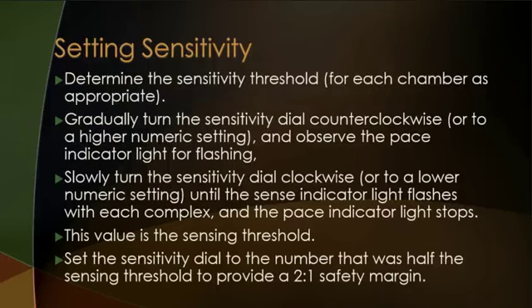So with setting sensitivity, you're going to determine the sensitivity threshold for each chamber as appropriate. Then you'll gradually turn the sensitivity dial, which is the very bottom dial, counterclockwise or to a higher numeric value, and observe the pace indicator light for flashing. You will slowly turn the sensitivity dial clockwise, or to a lower numeric value, until the sense indicator light flashes with each complex and the pace indicator light stops. So this value is your sensing threshold. Then set the sensitivity dial to a number that is half the sensing threshold to provide a 2-to-1 safety margin.